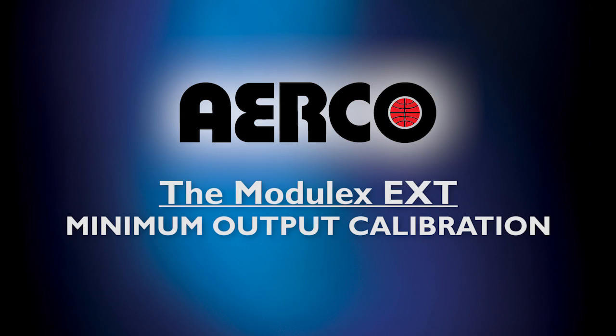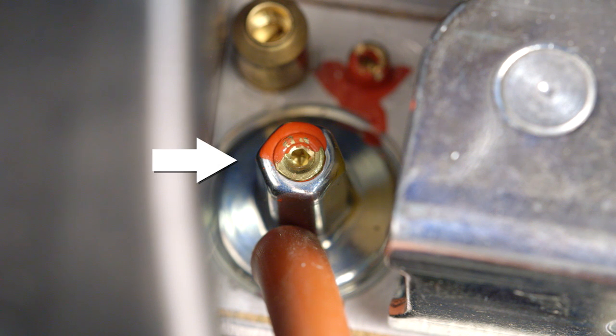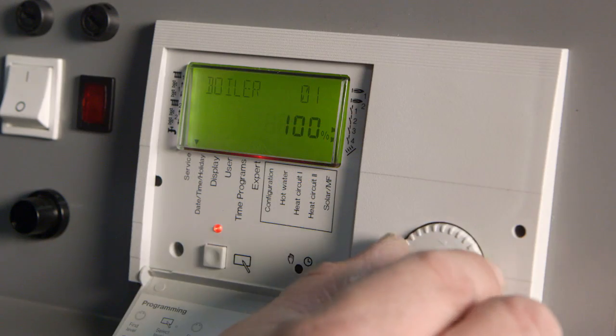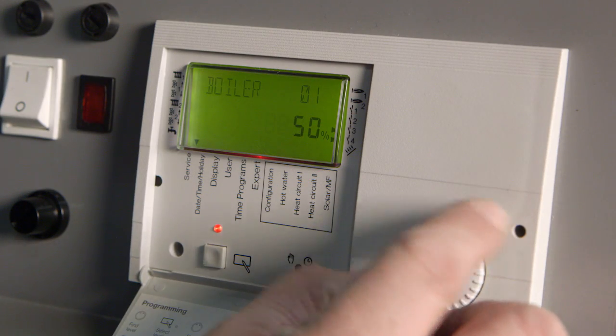Now that your unit's calibrated for maximum output, you must calibrate for minimum output. The screw requires a metric Allen key to adjust the minimum output. The bottom screw is for your minimum adjustment, as indicated here. Set the burner for 10% fire rate.